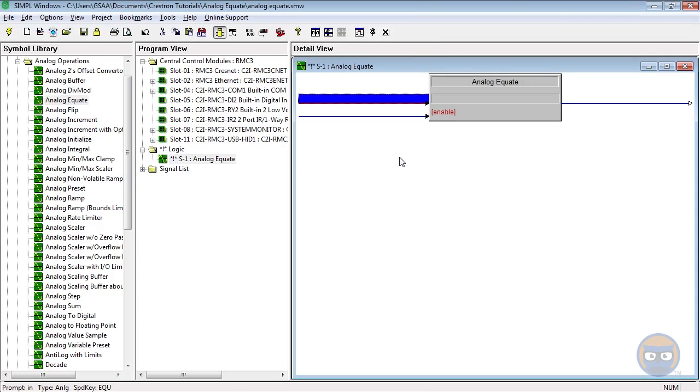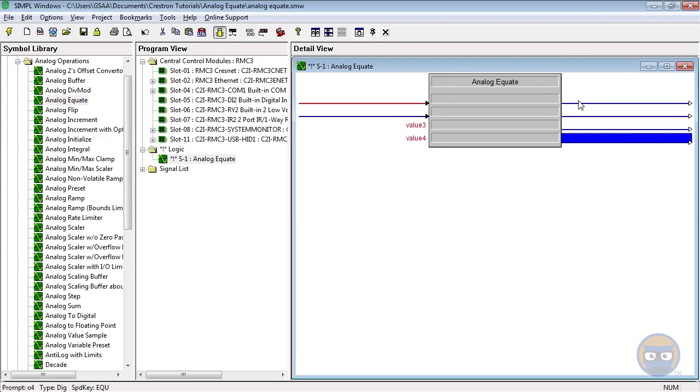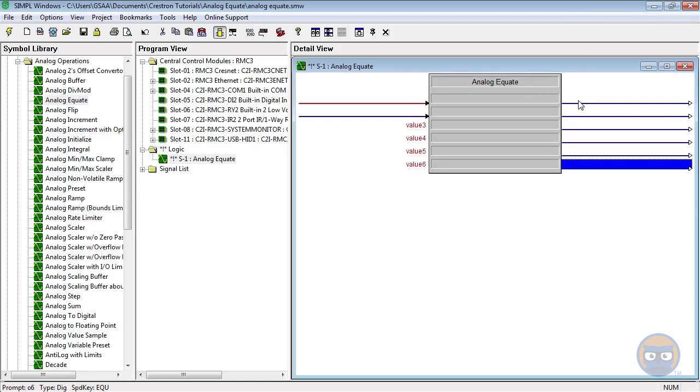The analog equate has one digital input and one analog input. It also has an expandable number of digital outputs with one parameter for each output. When an analog value is received as an input, it's compared to every parameter, and any parameters that match the input cause their outputs to go high.